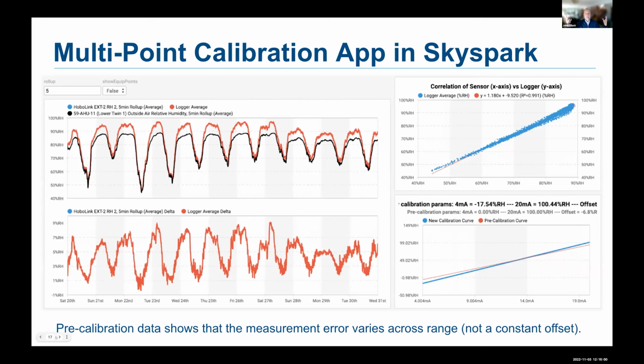But here's a sense of how it all comes together. Again, this is all in SkySpark. So we've tried to make this an efficient process. So you have the data coming from the Hobo data logger. It's coming through the cloud, and it's integrated, and it comes into SkySpark, and then we connect it up with the sensor point in the air handler. And so now they're coming together. You can see this as a trend here, and you can see it as a correlation scatter plot.